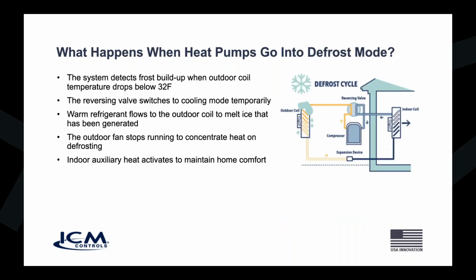So here's again a little picture talking about what I just explained to you previously: the system detects frost buildup when the outdoor coil temperature drops below 32 degrees. So you've got your outdoor coil, and you're going to go into a defrost cycle when a coil temperature sensor senses that the outdoor coil is too cold and that frost could build up on it. So then what's going to happen is a reversing valve in your heat pump is going to switch the refrigerant flow so that the outdoor coil now becomes the indoor coil, and the indoor coil becomes the outdoor coil.